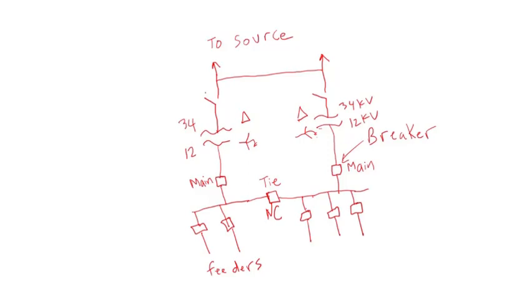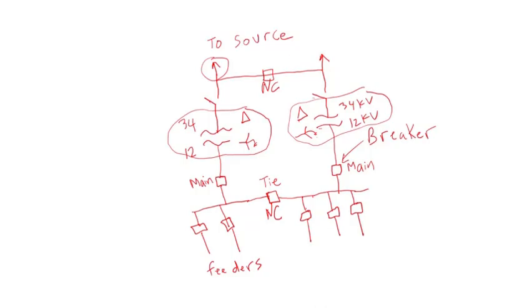We have two identical transformers here: 34 kV delta on the high side, 12 kV grounded Y on the low side, connected in parallel. On the high side I'm showing switches — in reality you might have breakers that are normally closed to establish the parallel condition. You might have two lines or two sources, depending on how much redundancy you want. If you only have one line and you lose it due to a fault, lightning damage, or similar, you'll lose the entire substation and the load will have to be served from somewhere else.